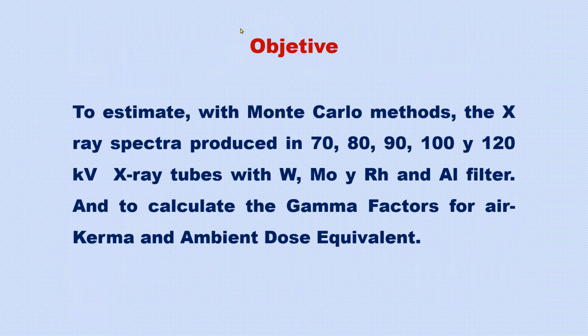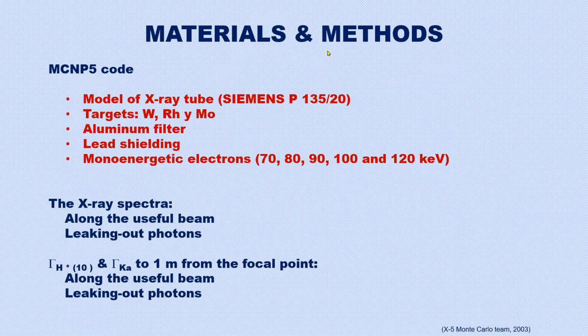So the objective of this work is to estimate with Monte Carlo methods the X-ray spectra produced in 70, 80, 90, 100, and 120 kilovolt X-ray tubes having tungsten, molybdenum, and rhodium targets and aluminum filters, and to calculate the gamma factors for air kerma and ambient dose equivalent. For the materials and methods, we used Monte Carlo methods through the MCNP5 code, and with this code we designed the model of the X-ray tube, taking the technical information of this commercial X-ray tube.